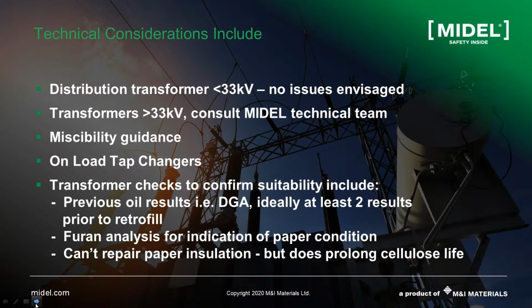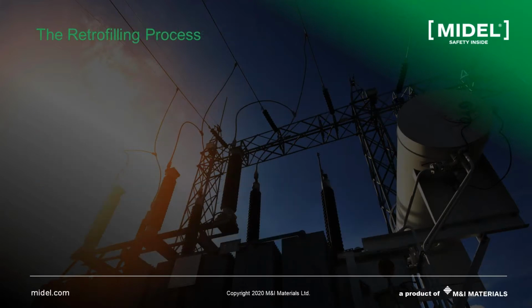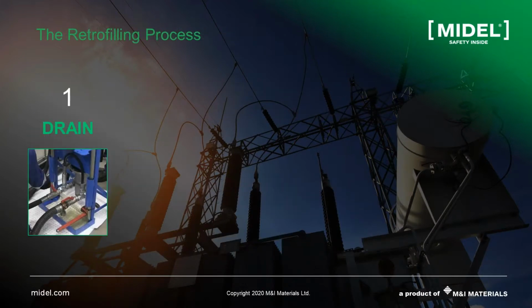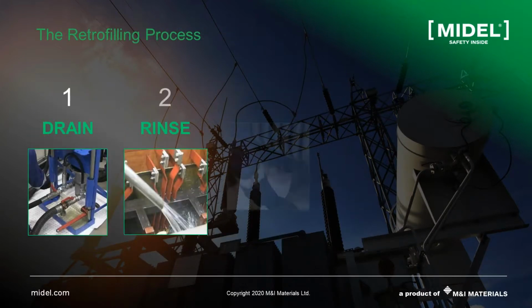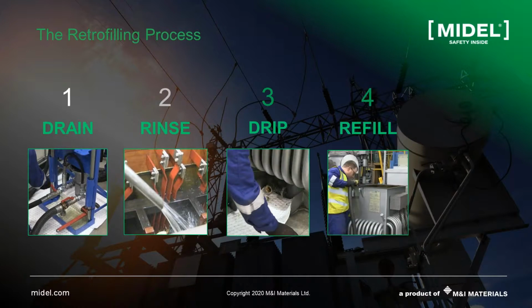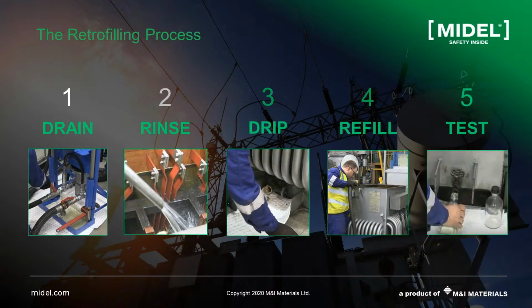After that, we can go to the next slide, where I'd like to show you the process itself. The first thing, of course, is to drain the liquid from the transformer, like the mineral oil in this case. After that, if possible, wait a short time to let the droplets drip down from the wall, the windings, and the other internal construction.